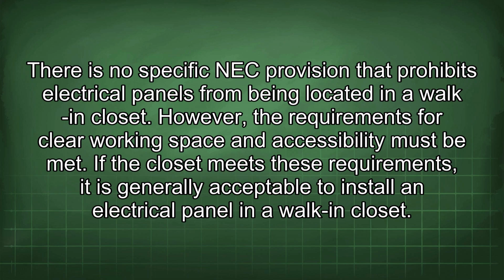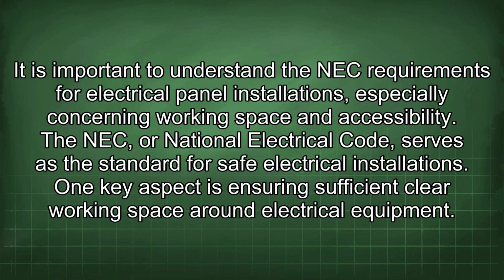There is no specific NEC provision that prohibits electrical panels from being located in a walk-in closet. However, the requirements for clear working space and accessibility must be met. If the closet meets these requirements, it is generally acceptable to install an electrical panel in a walk-in closet. It is important to understand the NEC requirements for electrical panel installations, especially concerning working space and accessibility.